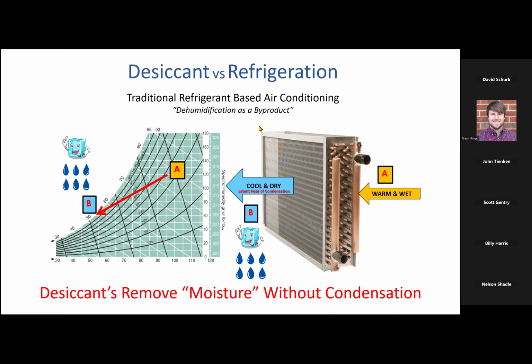One thing I want to point out, here's a little psychrometric bonus trivia for you today. Did you realize that when you take warm and wet air through a coil and you condense it onto this coil surface, you are actually putting sensible heat back into the air? Anytime you have a phase change where you take gaseous moisture and you condense it, there is a conversion of latent heat to sensible heat at the rate of 1,060 BTUs per pound. And that conversion of latent to sensible is imparted to the airstream. And this air leaving the coil actually instantaneously warms up quite a bit in actuality, but we never see it. We never know it's there. All we know is that I have cold and drier air leaving this coil.